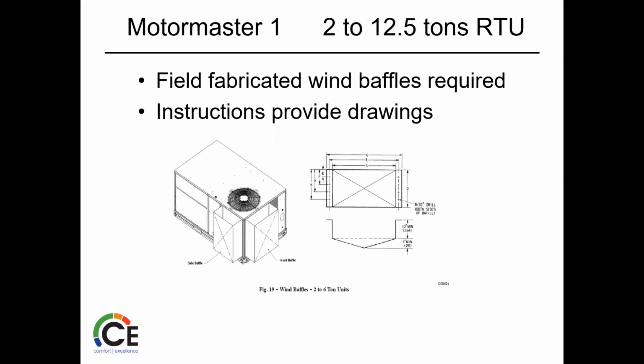So again, wind baffles for this low ambient control are needed, because we want to get that cold air off of that coil a little bit, so we can get those temperatures and pressures up and get some effective cooling going. Is it great cooling? No, but it's enough.